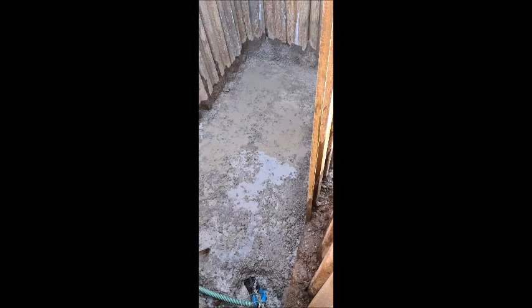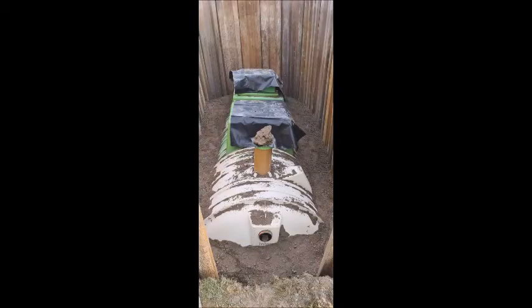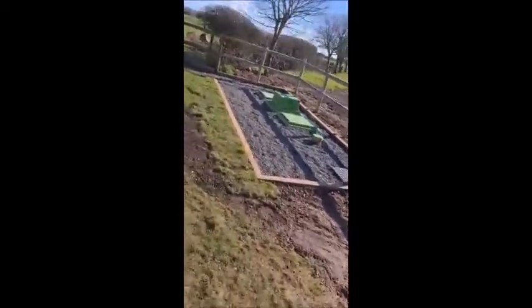The treatment plant was installed with a concrete backfill and a 300mm concrete base as per manufacturing guidelines. We finished it off with a backfill of pea gravel on the surface with geotex membrane underneath to make this a maintenance-free area, and finished with some sleeper borders to tidy everything up. There we have it — a shiny new Tricel system. Thanks to Stuart Golden for sorting that out — much appreciated.